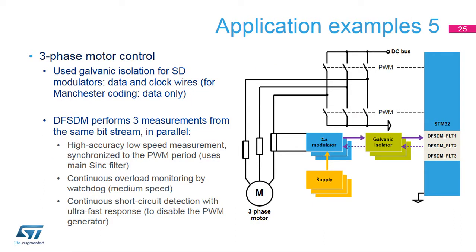This example is related to a three-phase industrial, high-voltage, high-current motor drive where floating shunts and galvanic isolation are standard. A single reading channel is represented here, while in the application two or three channels are used for current in addition to two or three channels for voltage. The currents are usually measured simultaneously by three DF-SDM channels, while the voltage can be measured sequentially with the same DF-SDM channel. The same bit stream is processed three times: first, for high-accuracy measurements, the main filter is used over a relatively long time, measured synchronously with a PWM period to avoid switching noise and have regular samples.